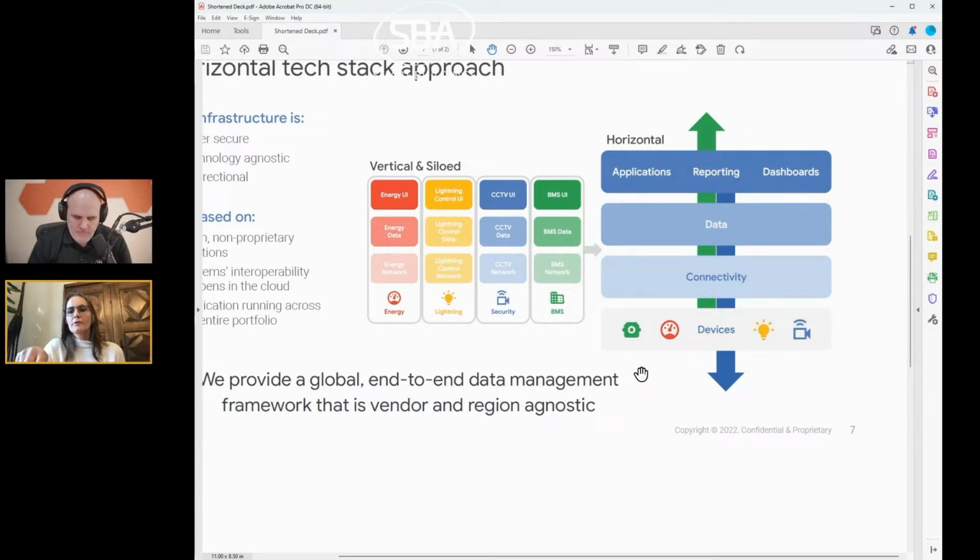We're also, if the device needs to be capable of talking to the cloud, not all of them are, but there's some level of gateway or some opportunity for the device to talk to the cloud. We also go to the vendor saying, we have this MQTT format, your device needs to be capable of doing it in what we call UDMI, Universal Device Management Interface format. So we're providing those guidelines.